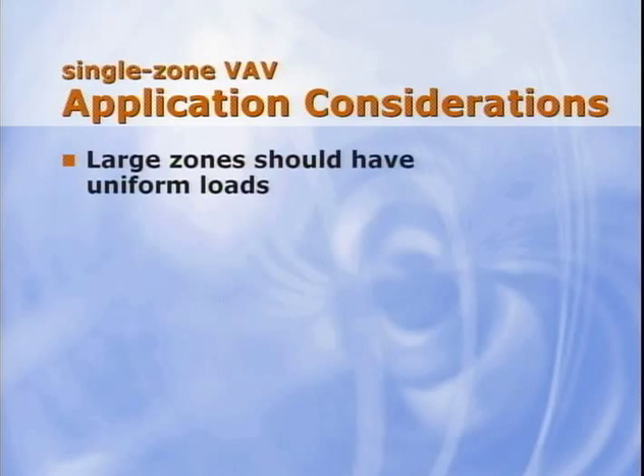In order to gain these benefits, the application must be suited to use single-zone VAV. So we need to consider the following. First, the loads throughout the zone need to be fairly uniform. A single-zone VAV system doesn't have the capability to satisfy simultaneous heating and cooling requirements. In addition, when the load in a large space isn't uniform, it may result in undesirable temperature variations in areas of the zone that are further away from the zone sensor.